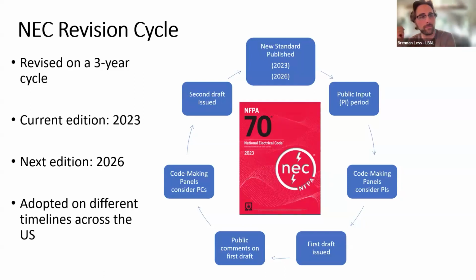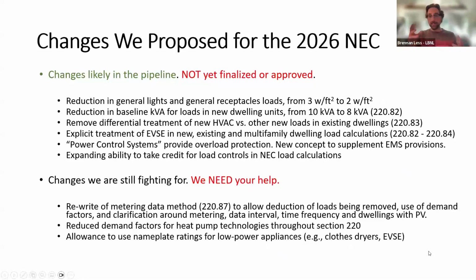Let's jump ahead. So ideas that we put out there for the 2026 code that seem like they have some support—they're not finalized or approved, but these have at least some good chance of passing—include reducing general lights and receptacle loads from 3 to 2 watts per square foot. We might see a reduction in baseline power associated with new dwelling units from 10 to 8 kVA. We're hoping for existing dwellings to remove the current different treatment of new HVAC versus other loads, trying to just treat new HVAC as if it was any other load. Instead of adding it at 100%, we would add it at something like 50%.